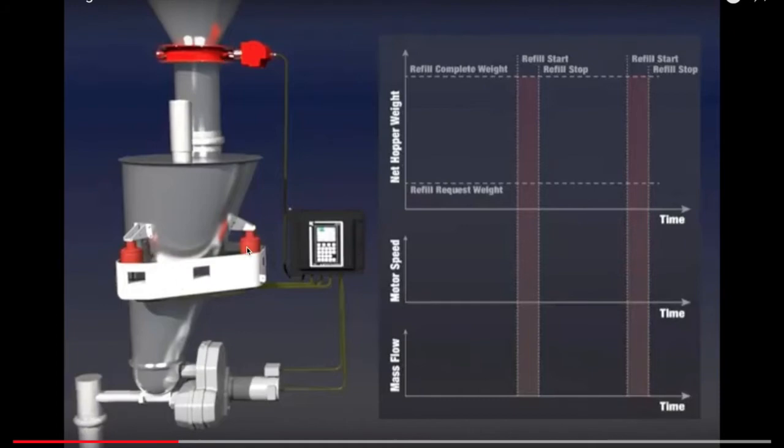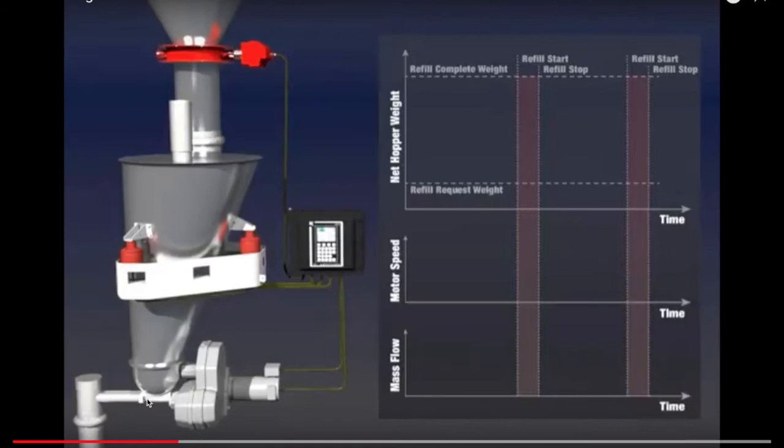It is on load cells. It's on three load cells, which are these red cylinders. And the weight is constantly being read. And it is going to measure a flow rate that exits the powder, that exits the surge tank through these screws at the bottom, and the screws are turning. The rate at which they are turning is what will depict the flow rate. The faster the screws are turning, the higher the flow rate.